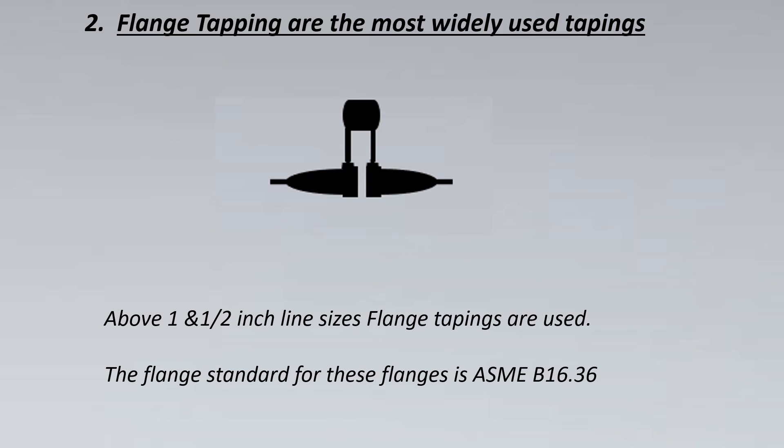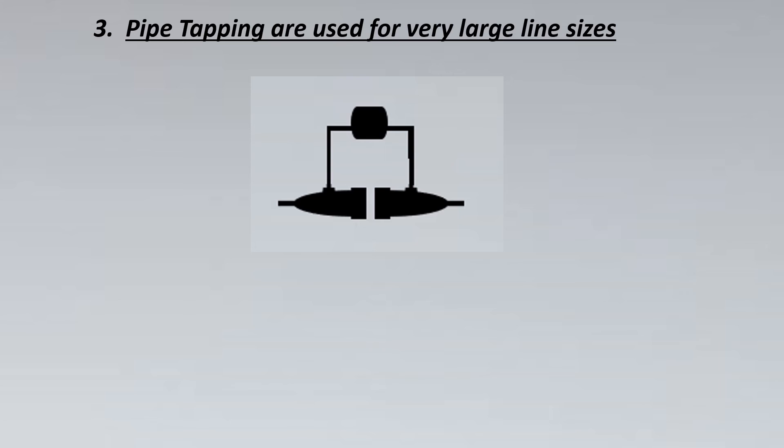This is the flange standard that we use for orifice flanges, and not ASME B16.5 or B16.47. Now let us look into the third type of tapping which is pipe tappings. These are specially used for very large line sizes. Why? Because the restriction that is created for such line sizes, the vena contracta is very far away from the DP device, so for that case we need to measure that DP at a longer distance from the restriction.